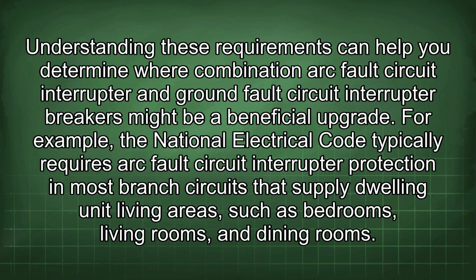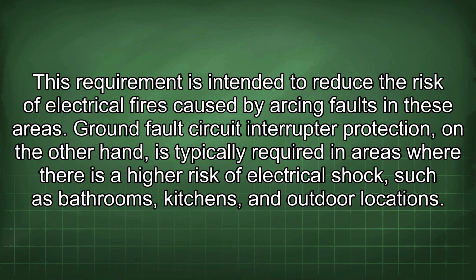be a beneficial upgrade. For example, the National Electrical Code typically requires arc fault circuit interrupter protection in most branch circuits that supply dwelling unit living areas, such as bedrooms, living rooms, and dining rooms. This requirement is intended to reduce the risk of electrical fires caused by arcing faults in these areas. Ground fault circuit interrupter protection, on the other hand, is typically required in areas where there is a higher risk of electrical shock, such as bathrooms, kitchens, and outdoor locations.